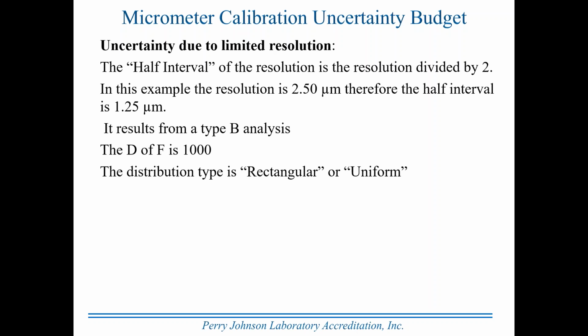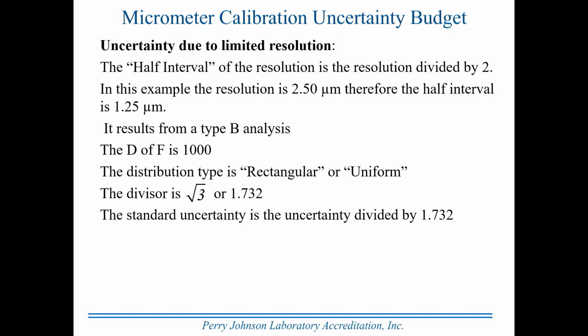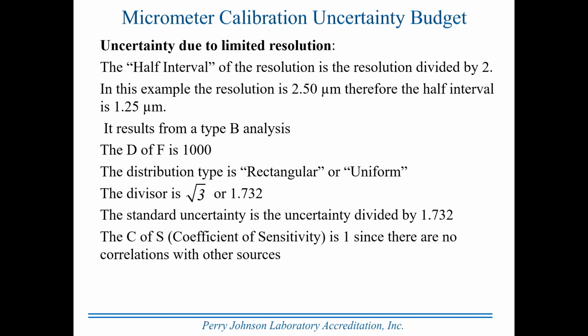Rectangular, when you're talking to metrologists. If someone calls it a uniform distribution, they're probably a statistician. The divisor, in previous cases, we had a divisor of 2, which is typical. We had a divisor of 1 because we had calculated exactly 1 standard deviation. Here, the divisor is the square root of 3, which is equal to 1.732, expressed at 3 decimal places. The standard uncertainty is the uncertainty divided by 1.732.